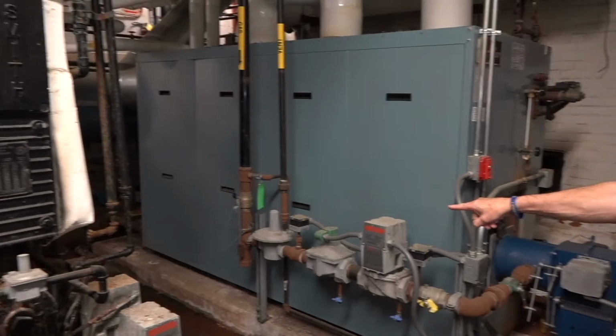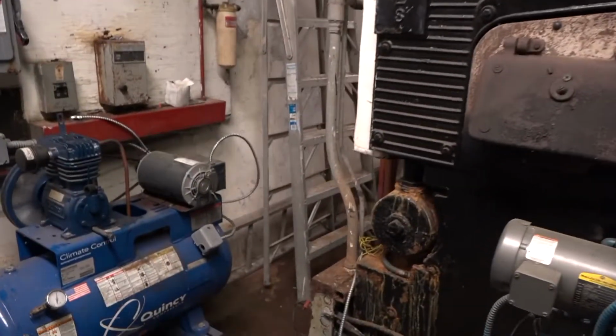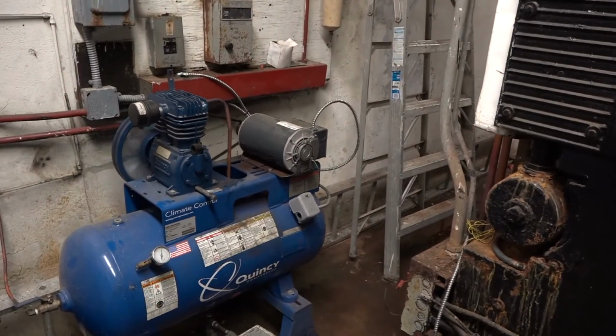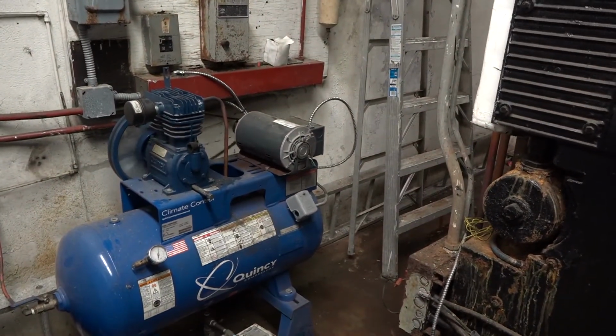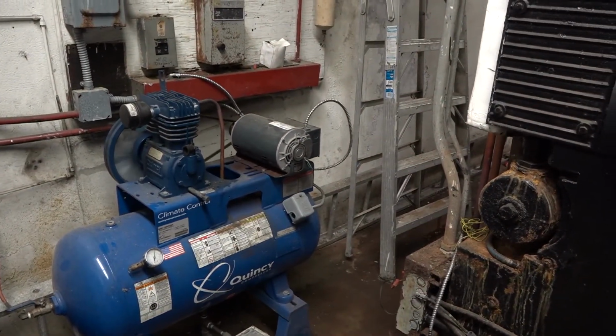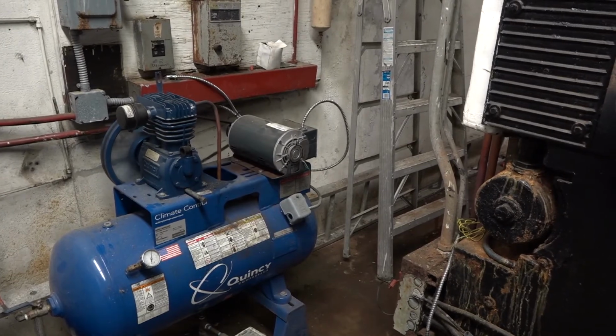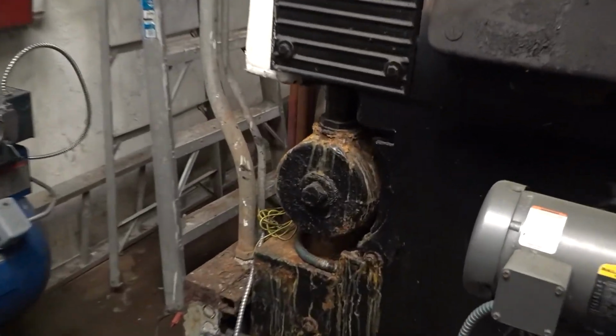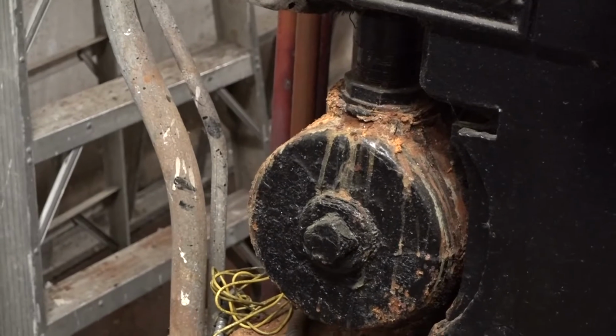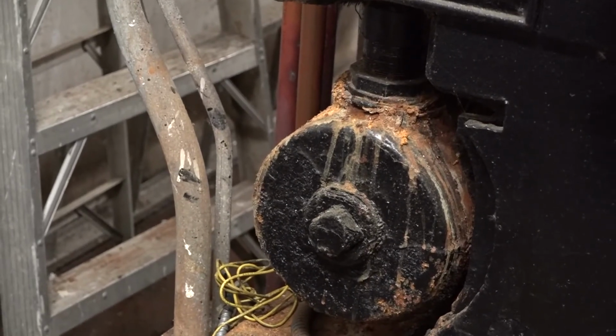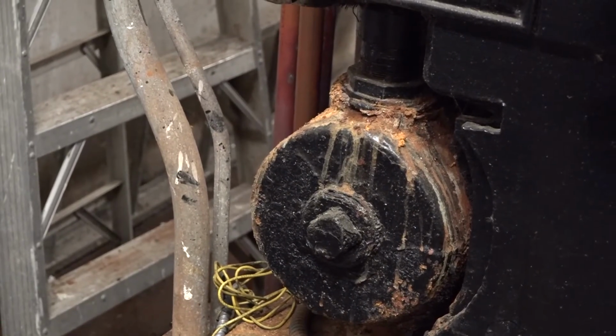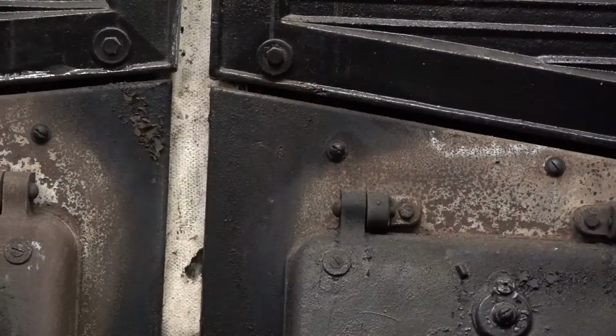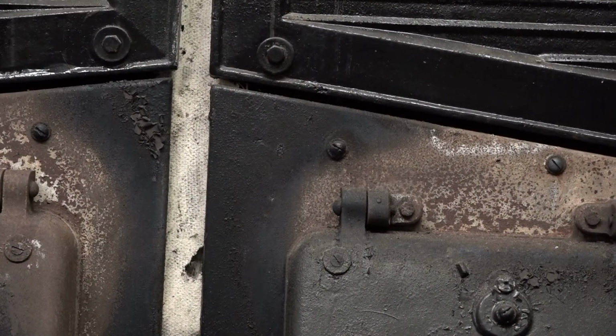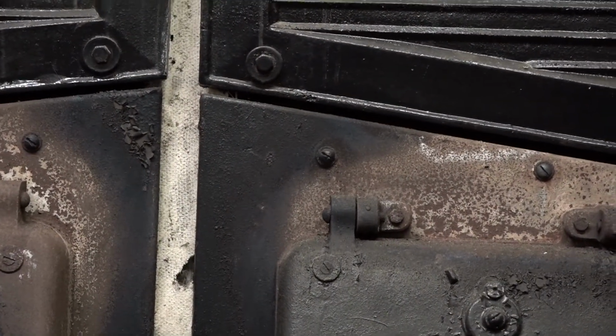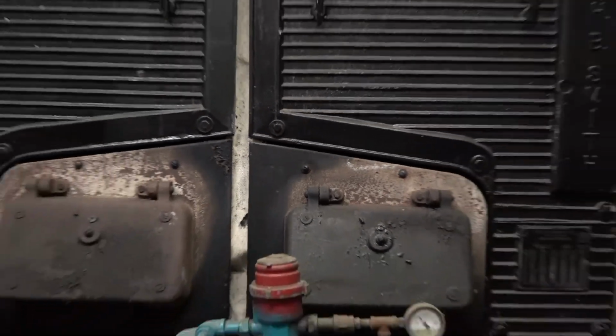Right. But I do know one of the heat exchangers up there for the hot water part of the building has failed. So we're only running on one heat exchanger right now. Okay. And they're so expensive. I'm trying not to spend the money on replacing it, because we'll just be throwing it away at this point. That's why we're going to try and get by with one boiler at each school. I'm fairly confident we'll be fine. Short of a catastrophic failure, you're not going to be down for any period of time.